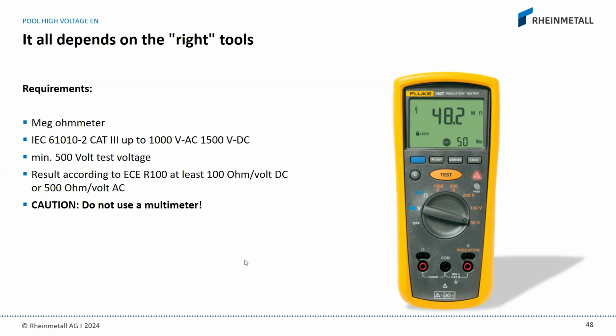Once we measure the isolation, we need a result of 100 ohms per volt DC or 500 ohms per volt AC. So let's say we have a 400 volt DC battery, then the correct result by measuring the isolation should be 400 volts multiplied by 100 ohms. I don't know the exact figure by heart, but it's a high number that results.